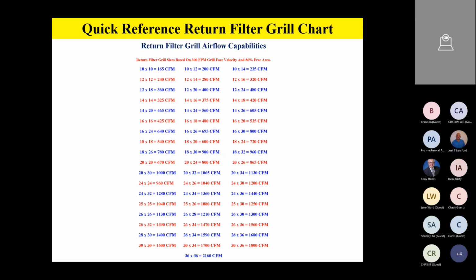1 square foot times 0.80, which would be 80%, times the velocity of 300 feet per minute. So let's take 12 times 12 equals 144 square inches, and we always have to get to square feet. And in this example, we divide by 12. That gives us 1 square foot. Okay, one more time, 12 times 12 equals 144, and then divide by 144. You always got to get to square feet. So to take any number of square inches, you divide by 144. That gives you the square feet.